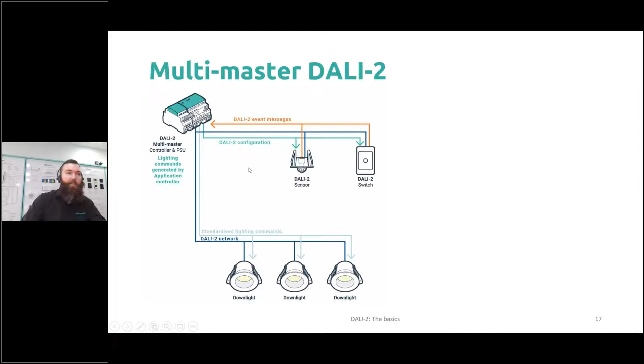The other advantage is that we have simplified cabling out to our building. Because we're moving all of these roles and tasks onto a single lighting control network, we can consolidate some of the systems. If we looked at what buildings may have looked like in the not so distant past, you'd typically have some sort of Ethernet or BMS backbone, then a dedicated line for your emergency devices, maybe a dedicated BMS system for your switches and sensors, and yet another gateway out to your lights on that line. So we could have 4 separate sets of cable running around the building that you've got to install, manage, and commission. You've actually got to pay commissioning engineers to go out and commission each of those independent lines.